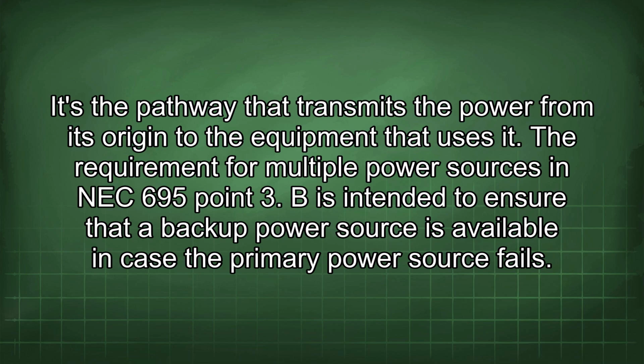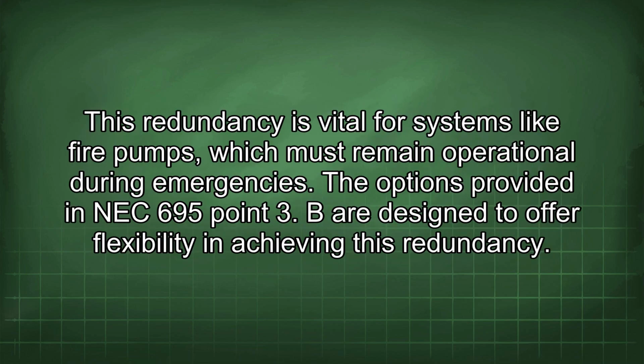The requirement for multiple power sources in NEC 695.3 B is intended to ensure that a backup power source is available in case the primary power source fails. This redundancy is vital for systems like fire pumps, which must remain operational during emergencies. The options provided in NEC 695.3 B are designed to offer flexibility in achieving this redundancy.